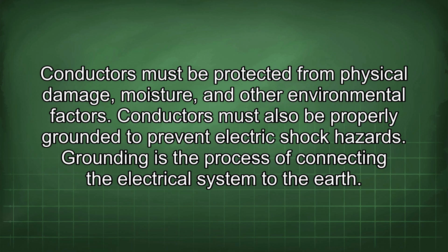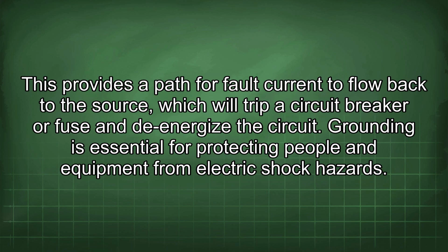Grounding is the process of connecting the electrical system to the earth. This provides a path for fault current to flow back to the source, which will trip a circuit breaker or fuse and de-energize the circuit. Grounding is essential for protecting people and equipment from electric shock hazards.